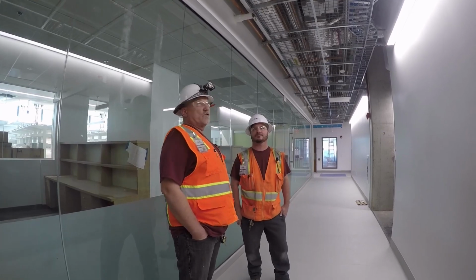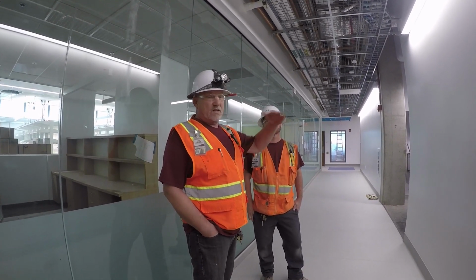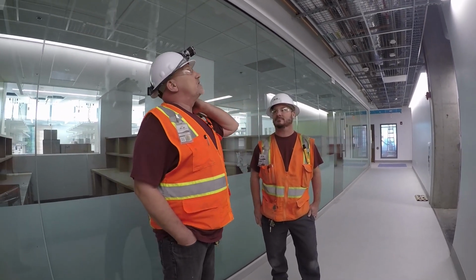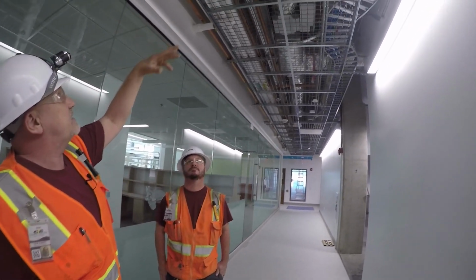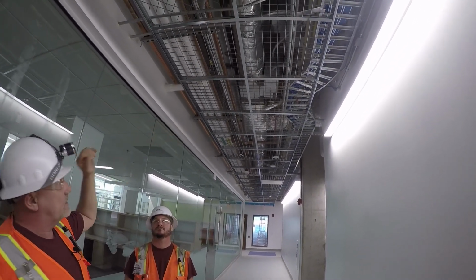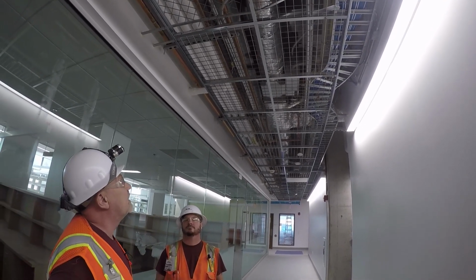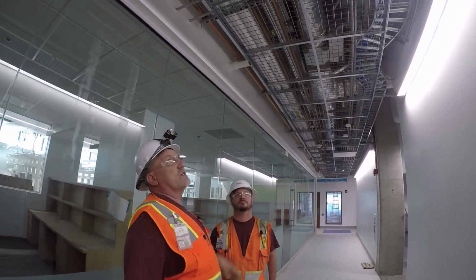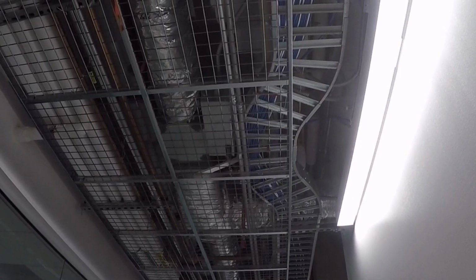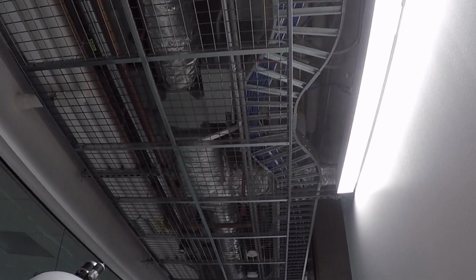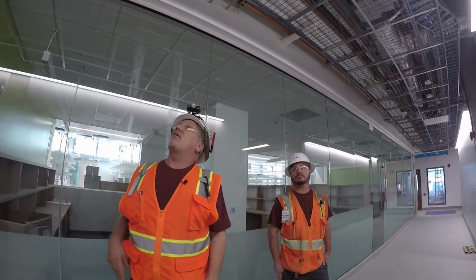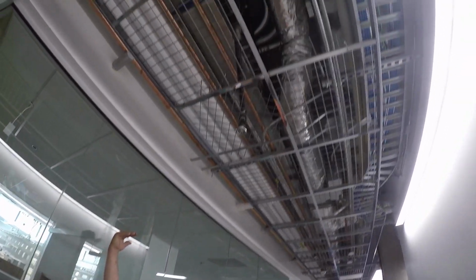We had a lot of challenges with this BIM project, which is layers and layers, and they put it together on a 3D computer to try to make everything fit in such a small area. We have HVAC, plumbing, electrical, low volt, and us, the higher voltage. It was very challenging. On my cable tray here, I had to maneuver it around this unit so somebody could get back up behind it and work on it. That was something the BIM didn't catch, so we had to modify it. Also, some of our feeder pipes on the BIM were running into the HVAC units, so we had to modify those. With some bends and turns and twists, we were able to make it work. As you can see, it's pretty crowded up there.